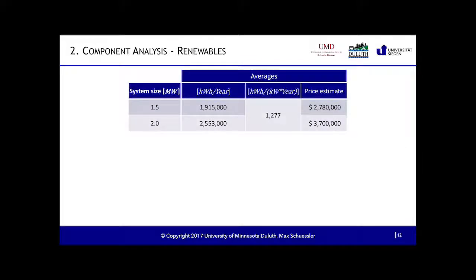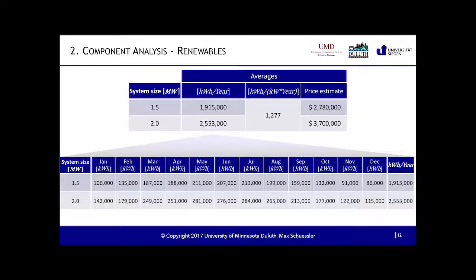And this is just the summary of my PV analysis, maybe an interesting number for people who are also studying PV in this area that I came up with. 1.3 megawatt hours per kilowatt per year, or 1,277 kilowatt hours per kilowatt a year that I can harvest with the installed capacity that we have up here. And I have an estimated cost of $2.8 million for the 1.5 megawatt system and $3.7 million for the 2 megawatt system. And those numbers are based on the newest numbers from the NREL and their quarterly numbers on their PV prices right now. And this is just an overview of what we could actually produce down there. And as I said already, I think that the 1.5 megawatt system as a conservative estimate is the estimate I will go with, to see on the lower end where I end up with the 1.5 megawatt.